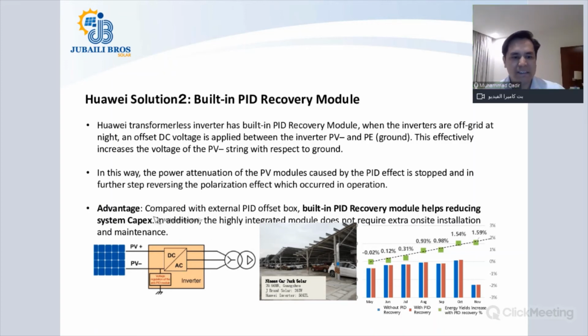The advantage, as compared to the external PID offset box, is that the built-in PID recovery module helps in reducing system capex. You are not using an additional device in order to cure this. You are not doing cabling, and also there is a lot of labor involved if you are doing the PID offset box recovery tab.